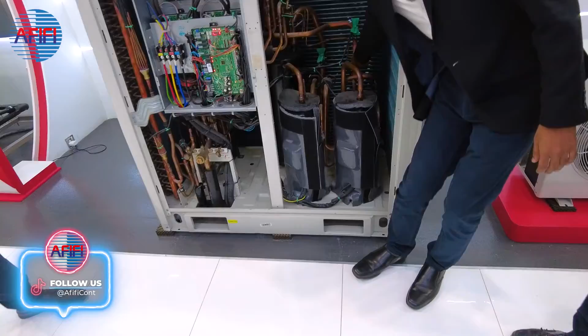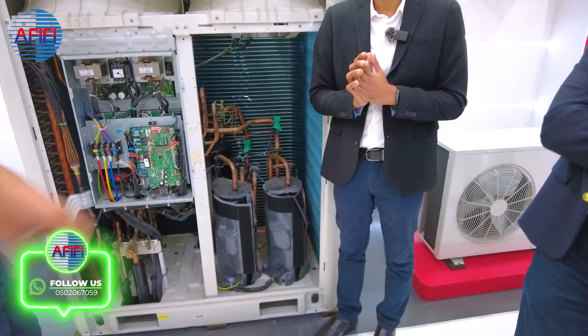Maybe it is more as a thermal insulation. Yeah, so we have these two compressors, and then there's an additional oil separator. So whatever balance goes out, the oil separator will also catch and return back. By these oil return backs, you regain back 90%. That's how the system is designed, and that's the only reason why VRF can go such huge lengths. Yeah, that's exactly how it does.